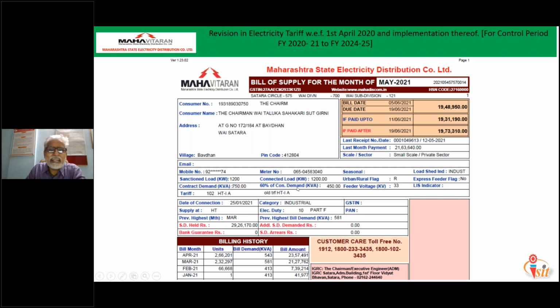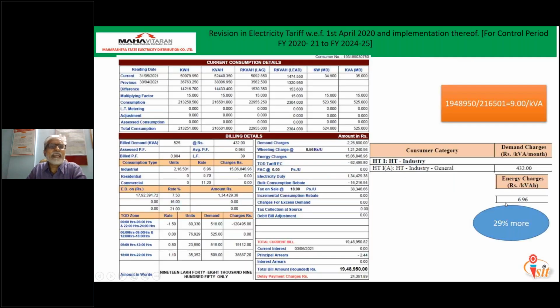Now as per this guideline, that is 60% of contract demand minimum they have to pay. So against this 750, the minimum 60% is 450. That means that for that particular month, whether they use anything from the 750 or not, they still have to pay demand charges as 450 multiplied by whatever rate is specified for that particular category. Now here it is HT, all the details are given. Now the calculation is done.